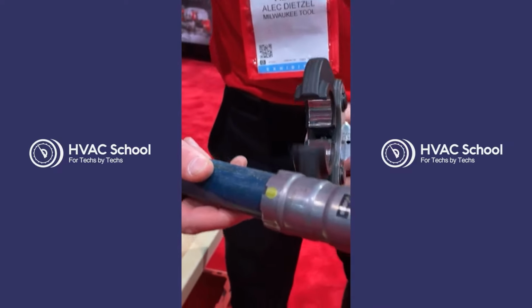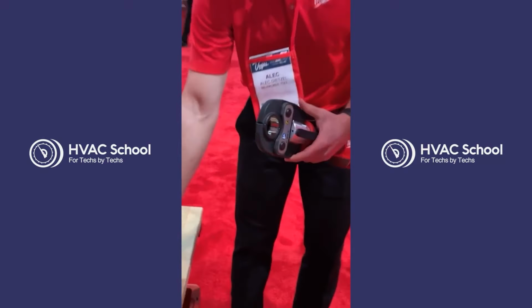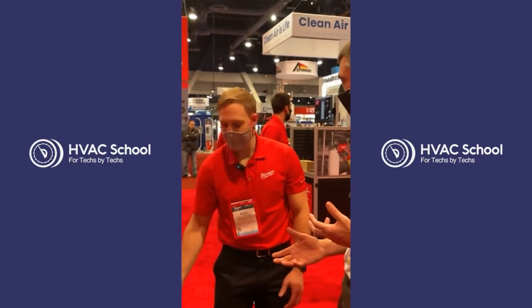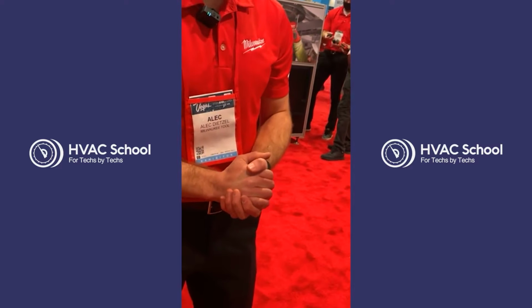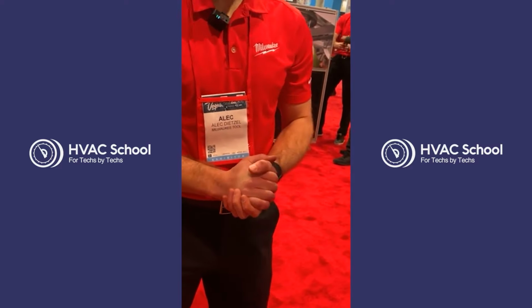That's a black iron pipe fitting. Before installing it, every fitting manufacturer has different instructions, so always consult those first. But generally, contractors are instructed to ream both the inside and outside of the pipe before making a connection, putting a slight chamfer on the edge so you don't chew up the O-rings when sliding the fitting on, and to have a smooth edge inside so you don't affect flow of gas or liquid going through.